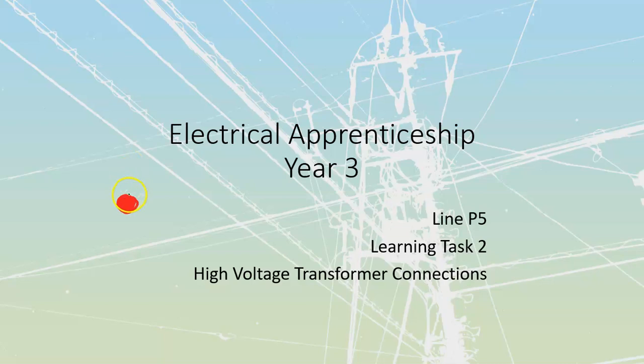Around the conductor, we're going to have a thin shield, made up generally of plastics impregnated with small amounts of metallics to make them conductive. You've probably seen this before when stripping out cables: right between the thick insulation around the conductor, there's a papery black layer that acts the same way as this.